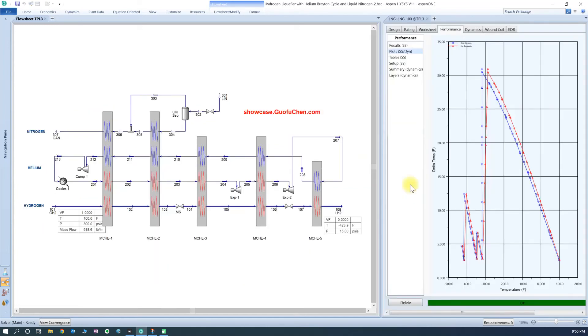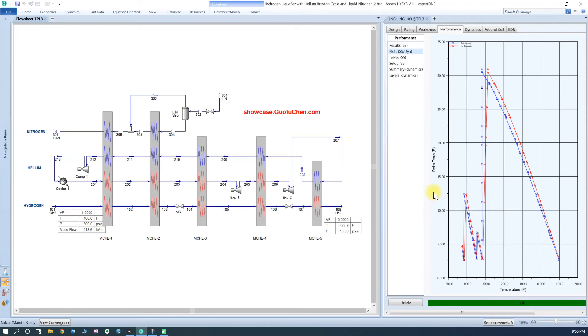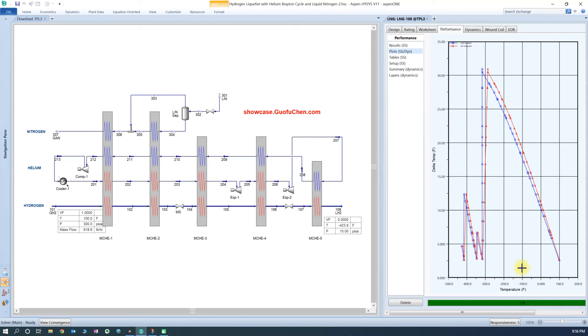For hydrogen liquefaction, one key parameter to watch out is the temperature approach. On this graph, the x-axis is the temperature, while the y-axis is the delta temperature, or temperature difference between hot and cold fluids. As you can see, there are four points that reach the minimal temperature of about two and a half Fahrenheit, so it is considered as an optimal design.